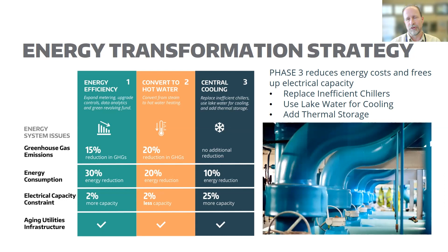The other key part is that those central plant chillers consume less electricity to produce the same or more cooling than the buildings do. Given our electrical constraint, this is a smart play, making the best use of the electricity we have by putting all of the cooling in the central plants. And the other benefit is all of that waste heat then also goes back to the central plant. So one theme in the energy strategy is to centralize the cooling and maximize the capacity we have in our two central plant buildings.